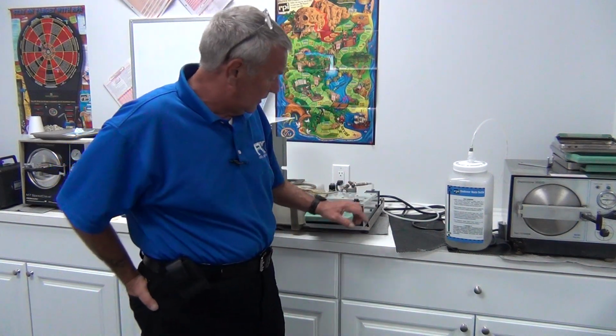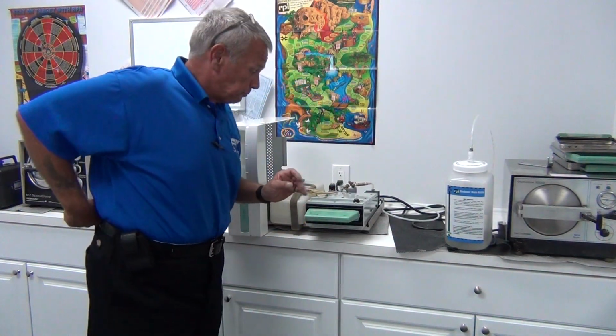Your main issue with this sterilizer is going to be the cassette gasket, too much water in the condenser bottle, or lack of water in the condenser bottle, or a steam leak from your hose. Either one of these can throw an error code. These machines look intimidating, but they're actually very simple and easy machines. There's no cleaning to them whatsoever. Because you use distilled water and the instruments are scrubbed well, there's no need to clean this machine.